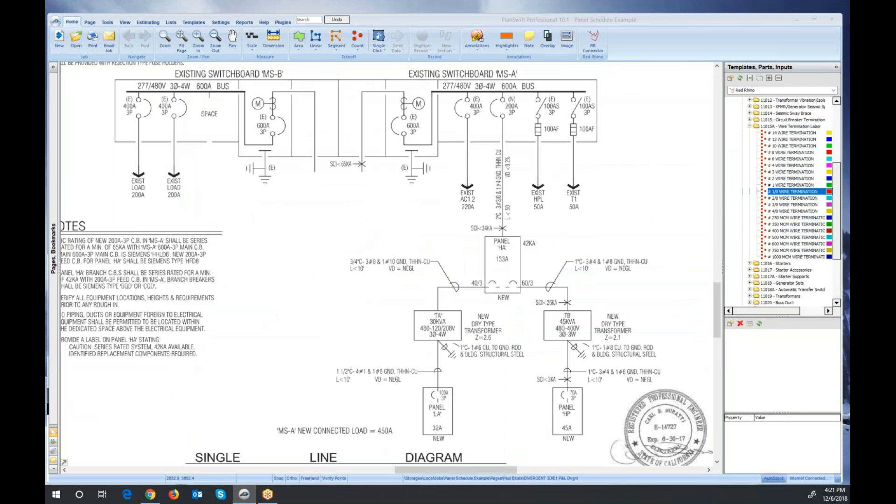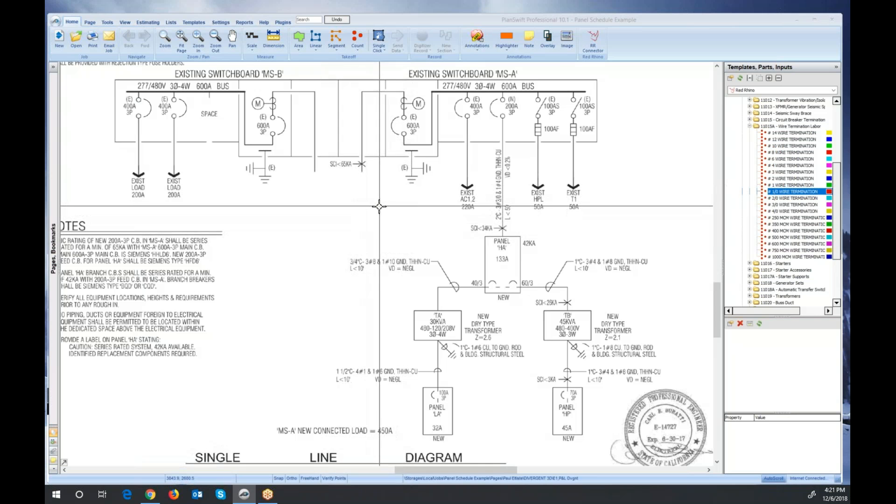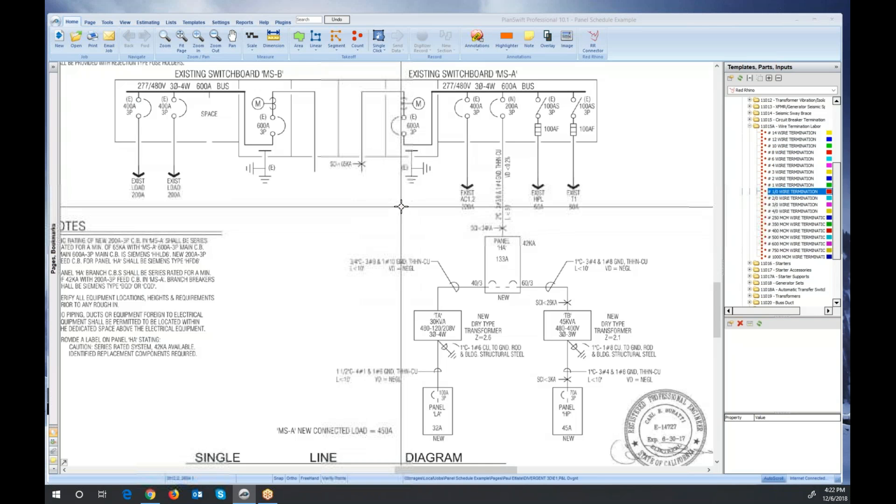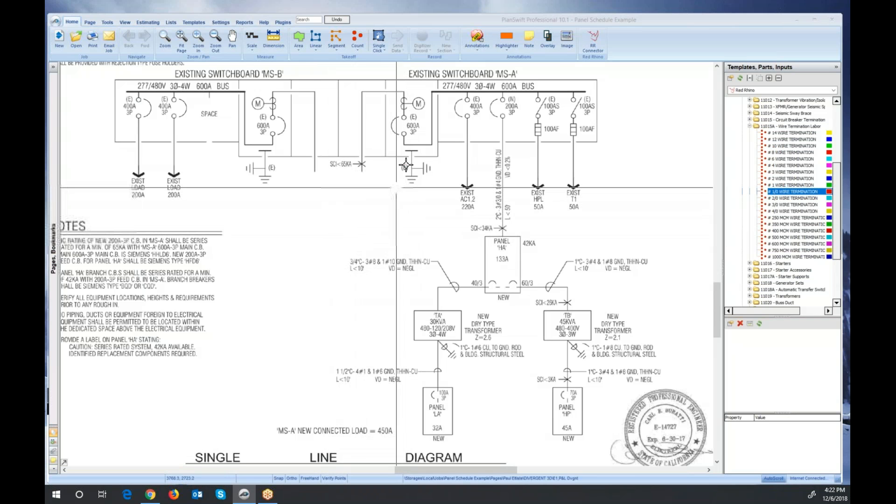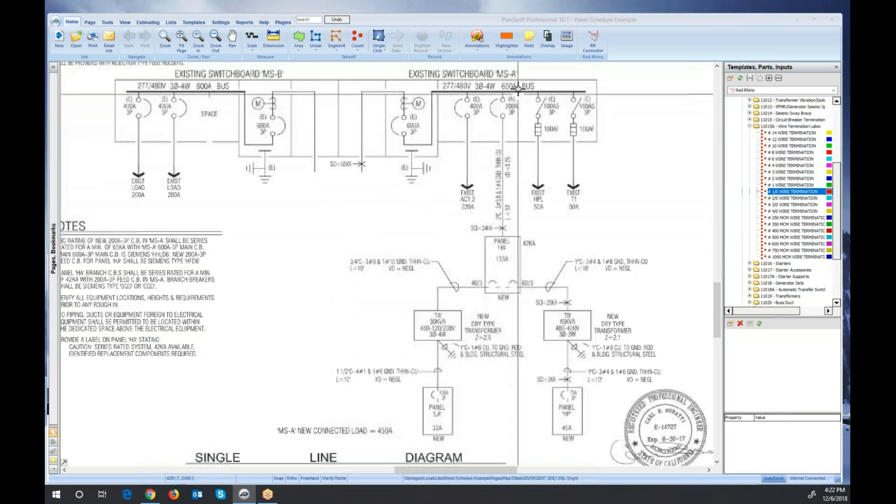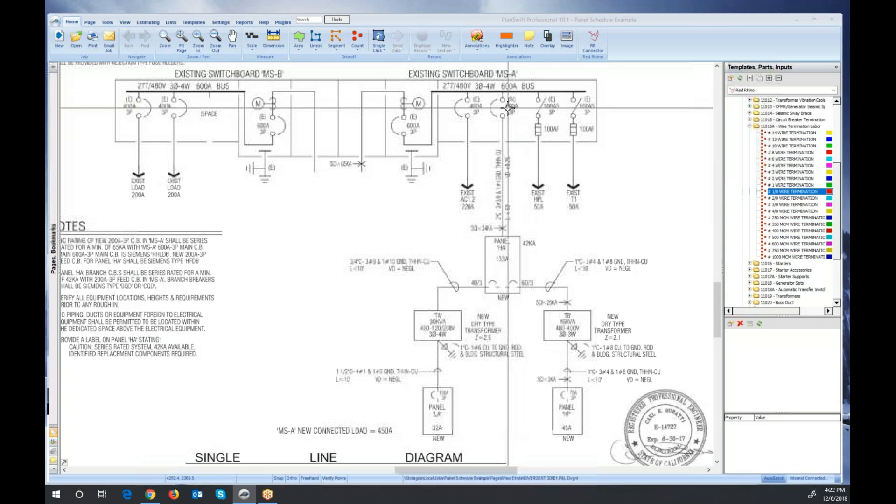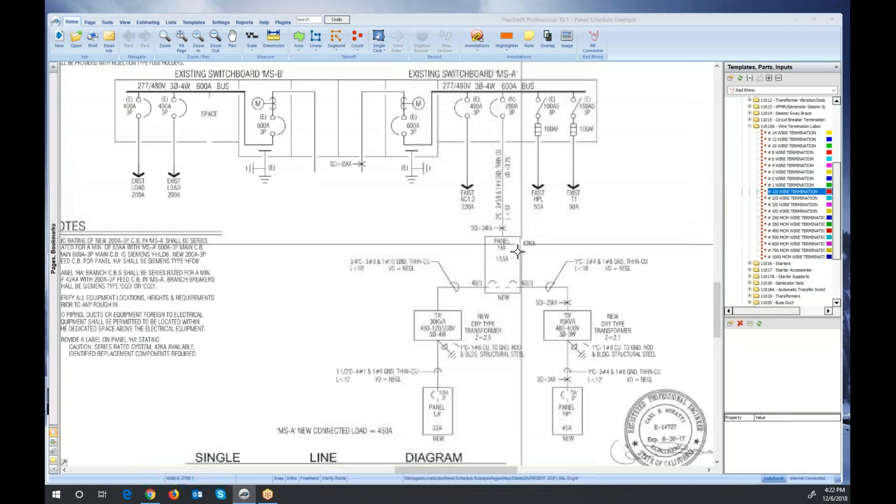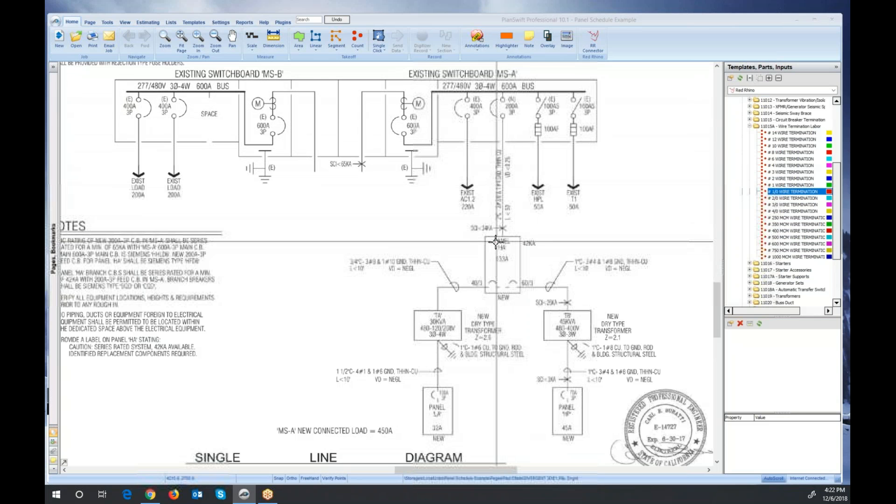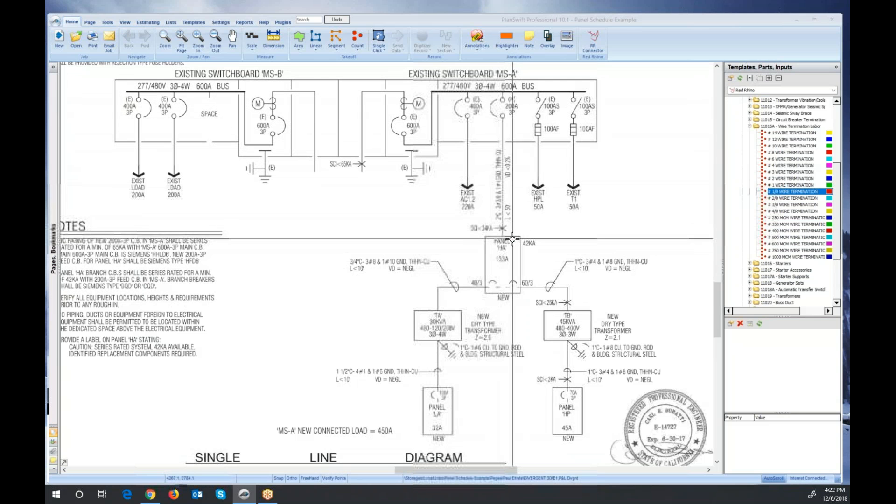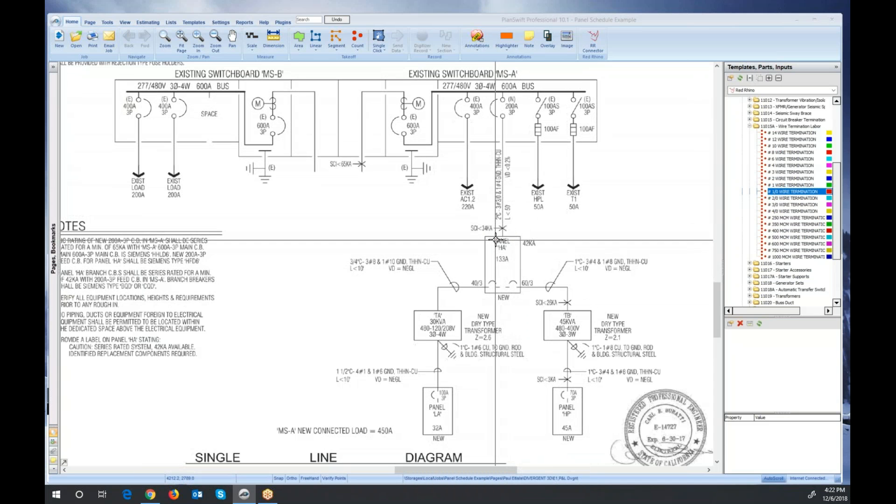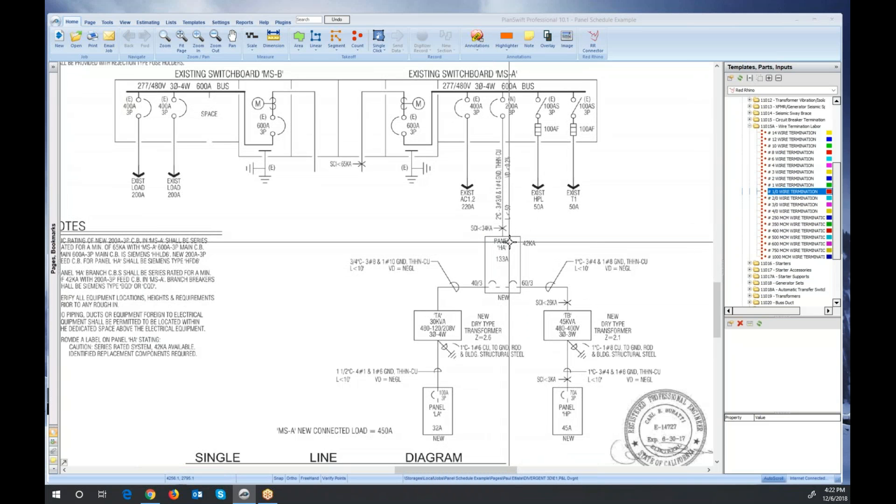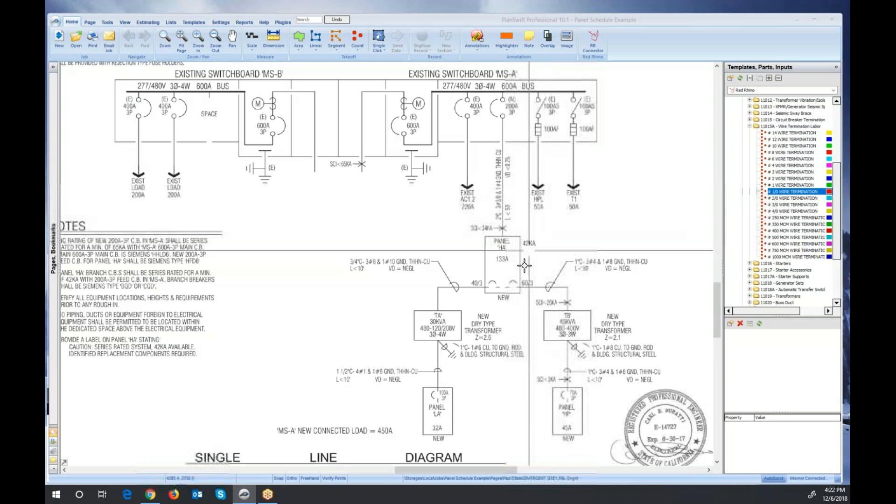Here's another example for wire terminations. I'm not paying attention to whether or not these are existing panels. If they were existing panels and it wasn't in your scope, of course you wouldn't count it. I'm showing you how to look for and find where wire terminations are necessary. This one shows a 200-amp circuit breaker with a feeder to a panel. And again, this panel is obviously main lug only. It doesn't have a circuit breaker here. So you would count wire terminations.